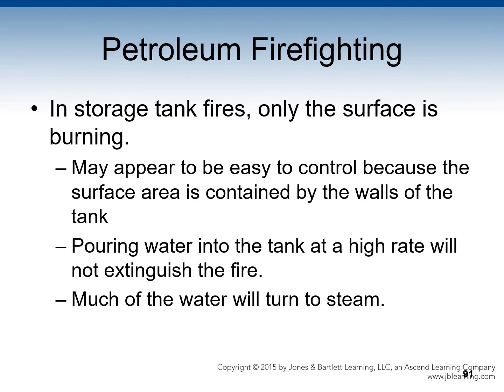Although these types of fires may appear to be easy to control because the surface area is contained by the walls of the tank, pouring water into the tank at a high rate will not extinguish the fire. Much of the water will be turned to steam by the heat of the fire, and oil floats on water, leading to three main problems in this type of firefighting: boil over, slop over, and froth over.